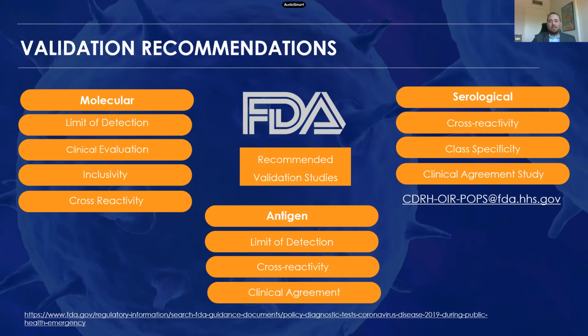Now, molecular tests have the most detail provided in the guidance document, and FDA provides guidance on acceptable sample types, use of contrived versus clinical specimens, required replicates for clinical testing, and then for cross-reactivity, a list of potentially cross-reactive organisms that should be tested in silico, as well as guidance on if there's greater than 80% homology, what type of wet testing should be conducted. Now, regarding the use of contrived specimens, FDA has indicated that this is allowed for molecular-based tests and antigen-based tests. However, it is not acceptable for serological-based tests.